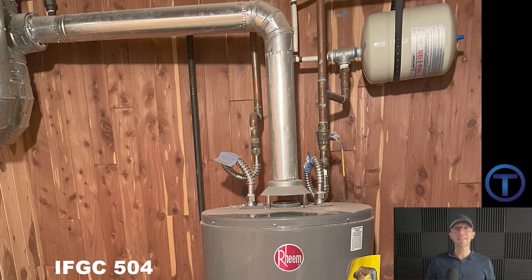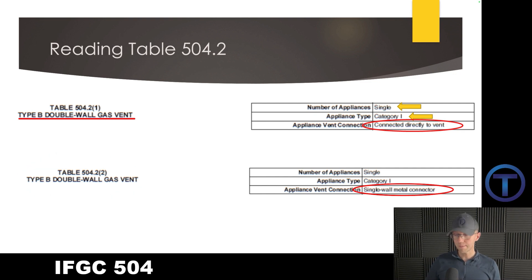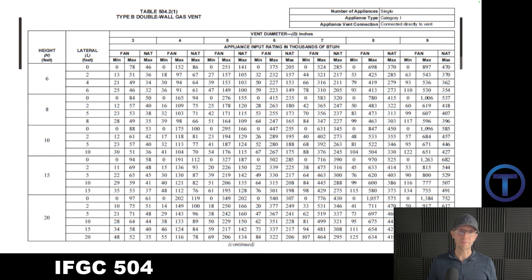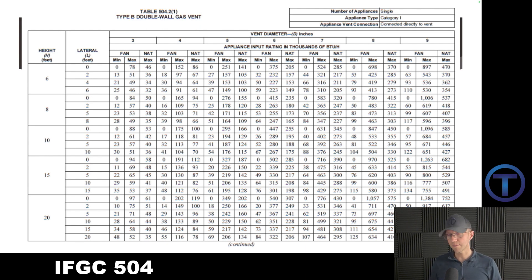Think about when you install water heaters. Most of the time we're running a single wall metal connector as our connection to the vent from the water heater. And that would be found on Table 504.2(2). But the way you know which one to look at is by focusing on those small tables. You have the overall section right up at the top on the right side, and that's going to help narrow down which of these many tables you're going to use. As you flip through, you'll find tables for masonry chimneys too, but we're not really into the sizing of those.